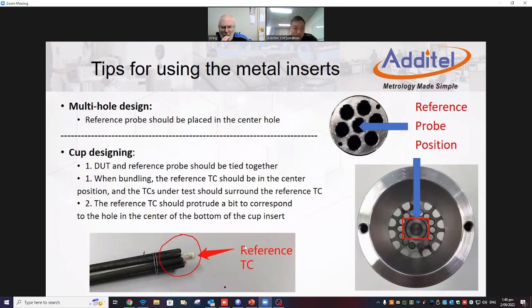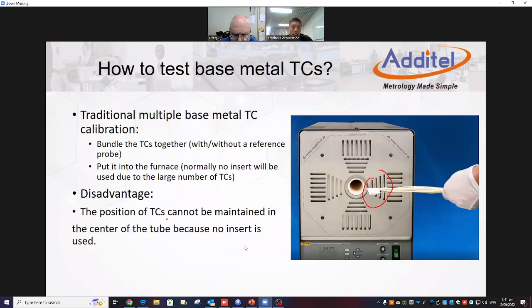As you can see in the picture right here, the probes are noble metal probes. This is definitely an armored probe like this. And the middle one is white in color because this is not the thermocouple itself. This is the thermocouple inside of the alumina sheath. That means we have the exposed thermocouple inside of the white alumina sheath like this. So when we test base metal, we normally make a bundle like this.